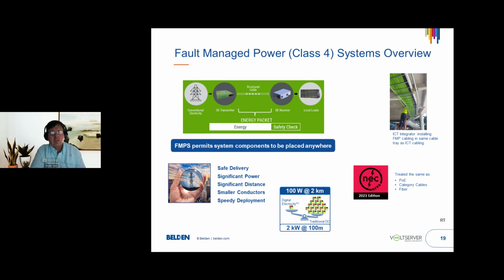And that's why the success in distributed antenna systems has taken off so well, because when you do an RF study to find out where my wireless strengths and weaknesses are, and you want to put an antenna where that weakness is, sometimes you would put a radio unit in that place or somewhere near, but you don't have power. With fault managed power, that requirement goes away, because now you can deliver that power and the data almost virtually anywhere. And just to make the point of how it's treated the same as PoE cables or category cables, I have here an ICT integrator installing a fault managed power cable in the same cable tray as fiber optic cabling. That's the difference between the colors of black and green in that tray.